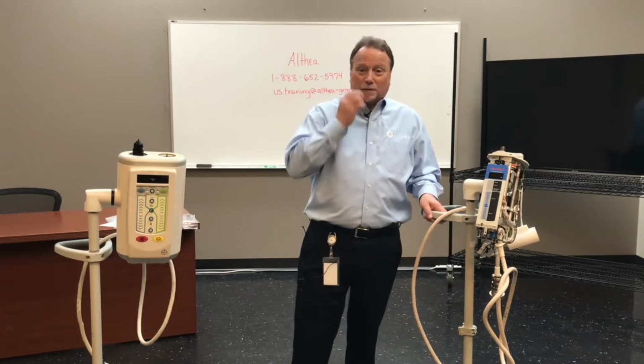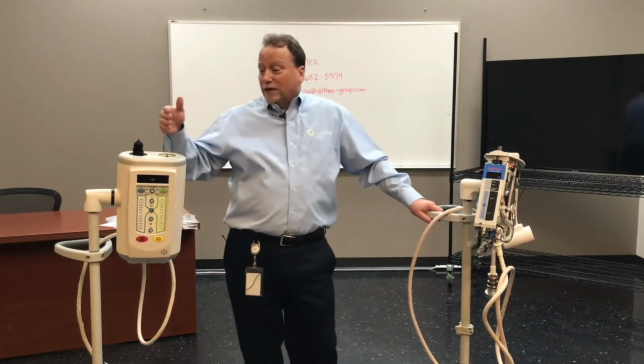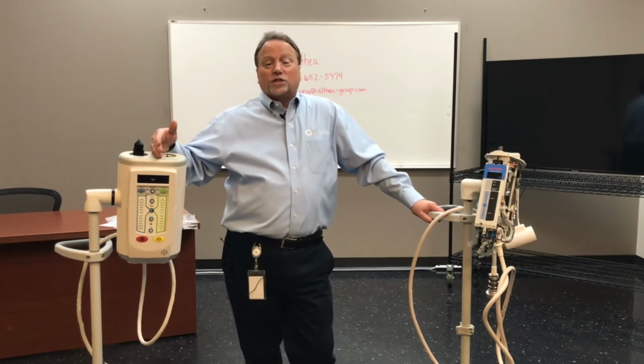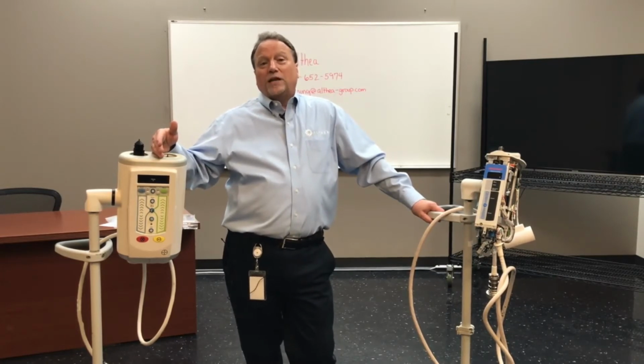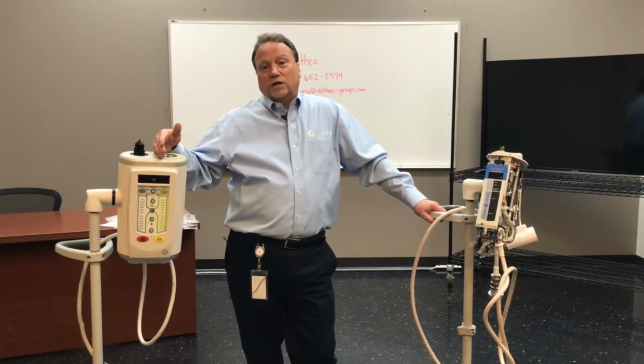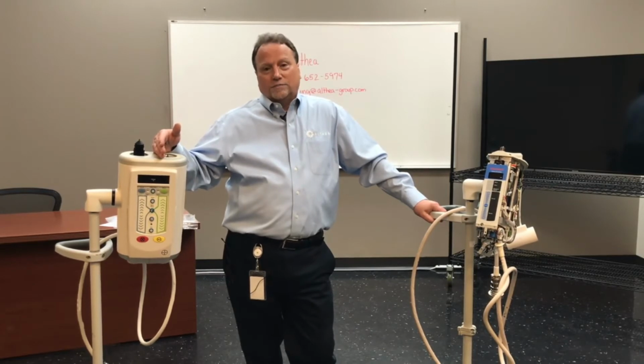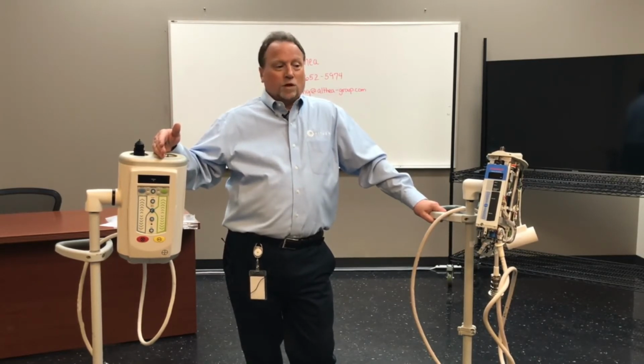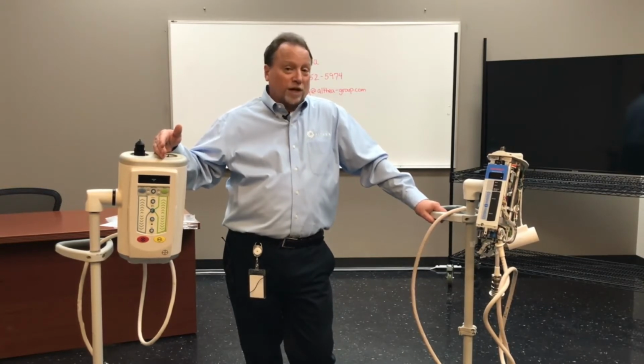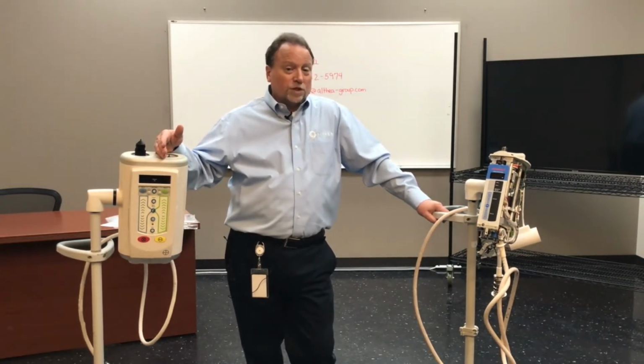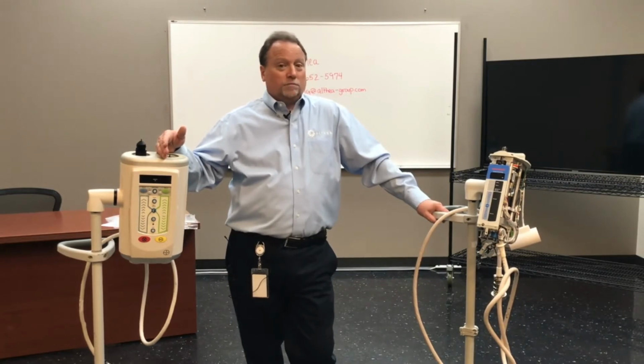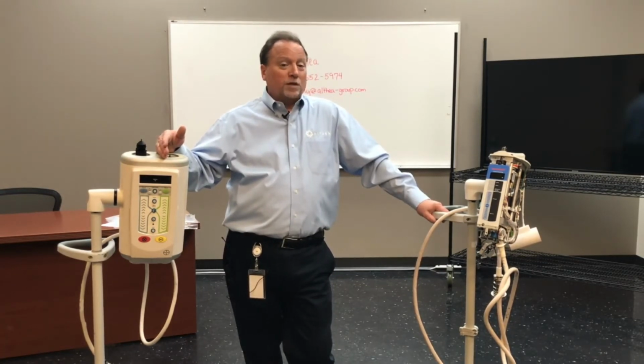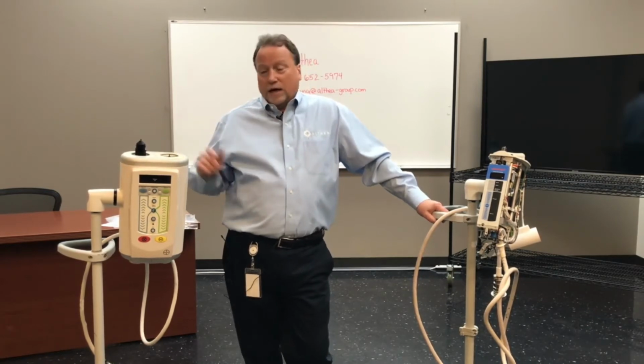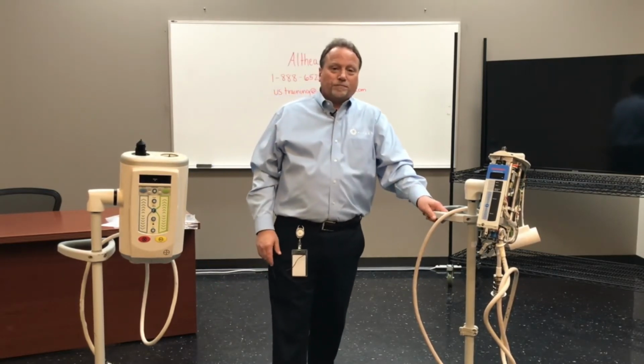But that's not the PM. That's most of the PM. Now, the OEM usually does not do that. If it's too bad, they'll come in and say, you need a new injector head. I can't work on it. And you say, well, okay, what does that cost? Well, those of you who have had to replace one, it's $12,000 for the injector head. They won't clean. If you're lucky, they may do some cleaning. If you're unlucky, they're going to walk in and say, I can't do a PM on this.